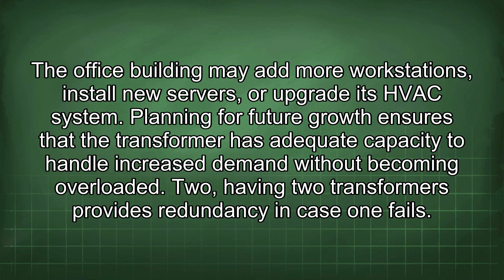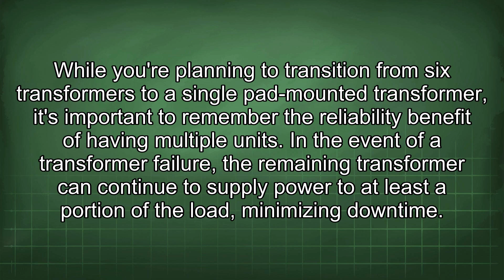2. Having two transformers provides redundancy in case one fails. While you're planning to transition from 6 transformers to a single pad-mounted transformer, it's important to remember the reliability benefit of having multiple units. In the event of a transformer failure, the remaining transformer can continue to supply power to at least a portion of the load, minimizing downtime. If the single new transformer fails, there would be a complete loss of power to both buildings.